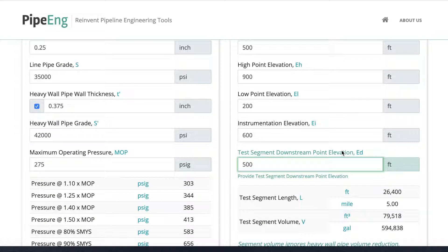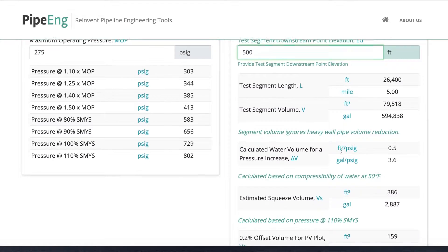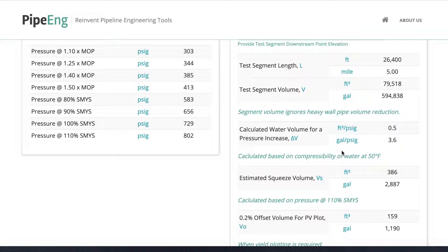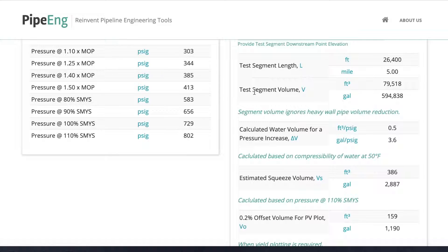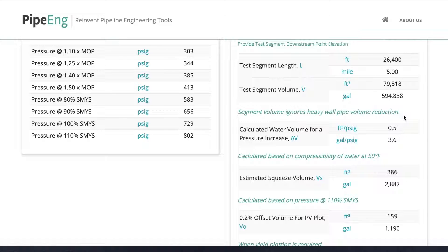Once we finish all the pipe profile and length inputs, let's take a look at the first result section. We can see we have test segment length, five miles as we put it in, and we have test segment volume. This is empty pipe volume that with zero pressure, obviously. We have a note here saying that segment volume ignores heavy wall pipe volume reduction. So if we have inputs about heavy wall pipe, that's usually a fairly short section compared to the entire length, so the volume reduction is negligible in this case.